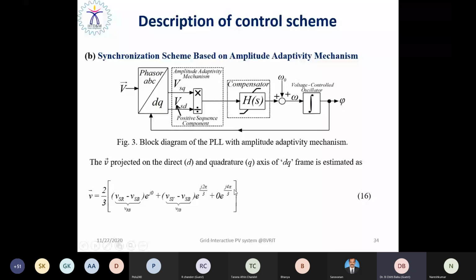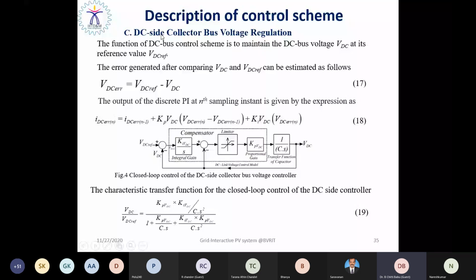And in the DC side controller, bus voltage regulation is very important, because it is contributing to active power control. So then the actual DC link voltage will be compared with the reference voltage of 690 volt. Then the error will be given to the PI controller, that includes the compensator, limiter and the proportional gain. Then that will provide a proper controller in the closed loop. So care should be taken while designing this controller, including the gain calculation for KP and KI. Accordingly, this control loop works, so that you are able to regulate the DC link voltage.